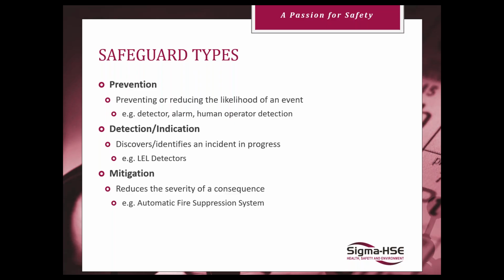feed. You've got gas detection in the area at 25% LEL. It alarms and alerts operators to know, there's an issue here, there's a leak, something needs to be done to address this. Detection, indication, something's already in progress, but you can detect and respond that way. Fire detection, if you've got pressure indication in a vessel that's not supposed to see pressure, maybe a vent stack, and then your mitigation, which is least effective, last ditch usually for your safeguards, and it reduces your severity.